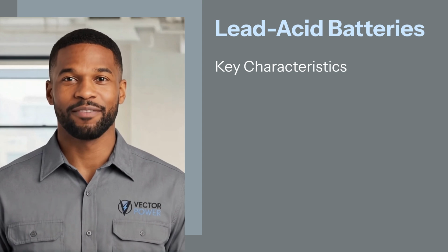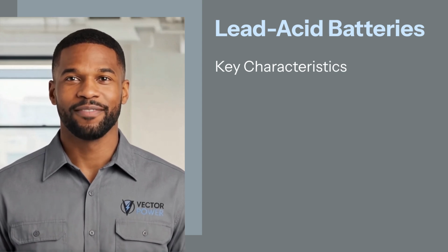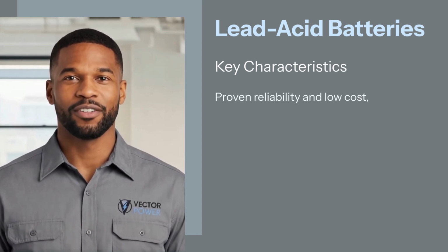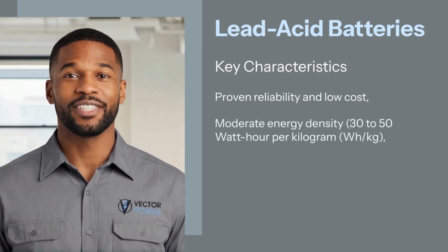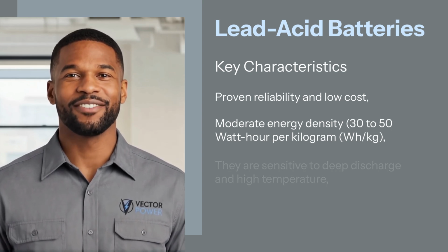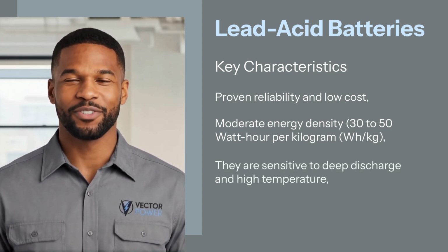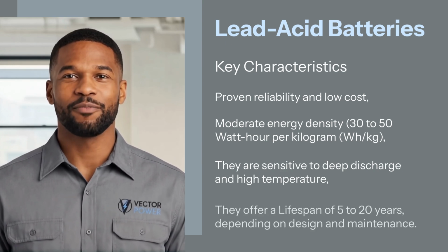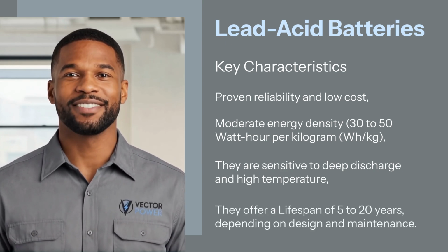Key characteristics of lead-acid batteries include: proven reliability and low cost, moderate energy density, 30 to 50 watt-hours per kilogram. They are sensitive to deep discharge and high temperature, and they offer a lifespan of 5 to 20 years, depending on design and maintenance.